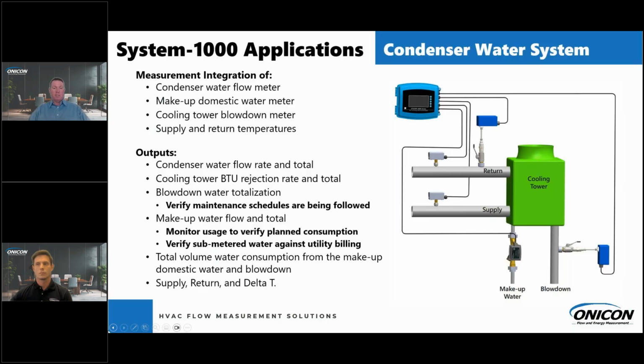But for this channel of the System 1000, we would have our condenser water flow rate and total. We'd have our cooling tower BTU rejection as a rate and total. We can have a blowdown water totalization, and that's great because that allows you to verify that your maintenance schedules are being followed and that your maintenance team is doing what you need them to do. You'll be able to track your makeup water as a flow and a total, and that allows you to monitor the usage to verify your planned consumption.